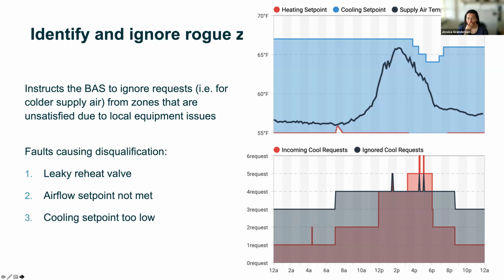In these plots, the dark shading on the bottom shows that it's only until about 4 or 6, late afternoon, where we're actually getting to a place where the requests are legitimate. So we see an impact on the top screen, with the set point coming down and then going back up. Day after day, unit after unit, this amounts to significant savings from addressing zones we know have other issues and shouldn't be pushing the whole system to max.